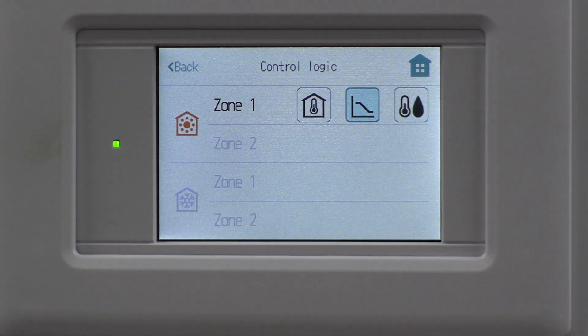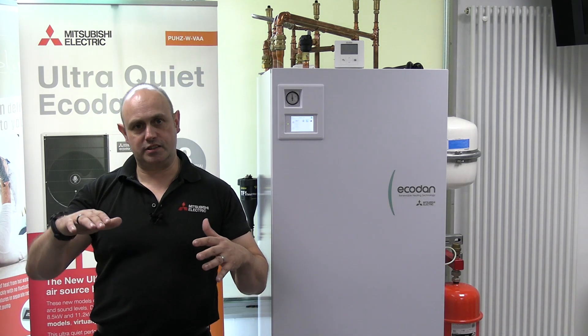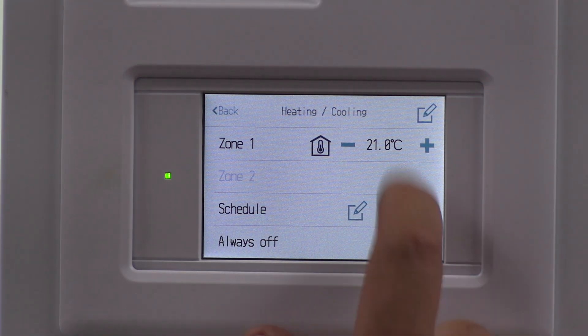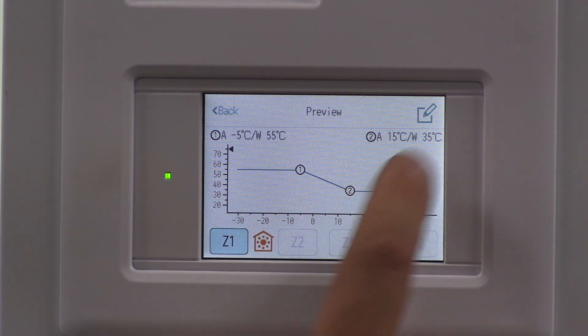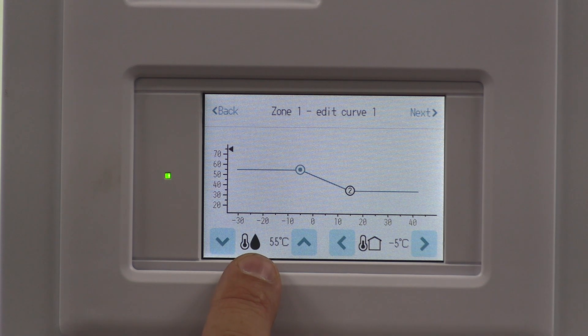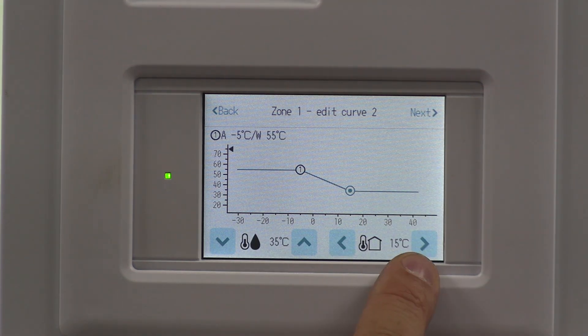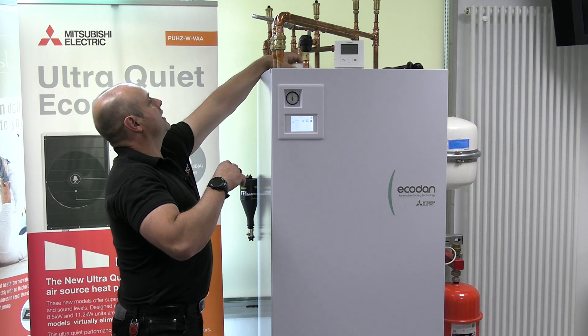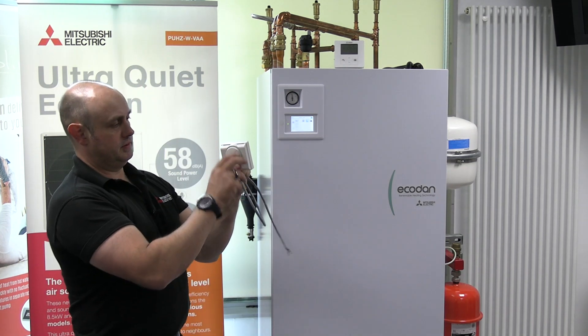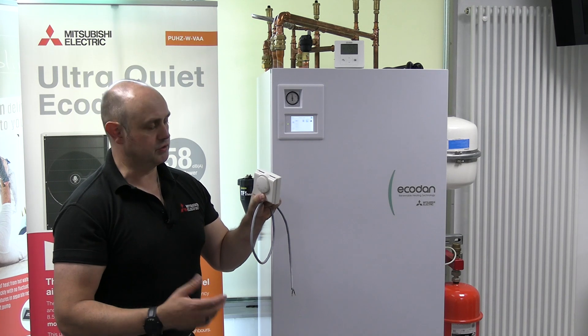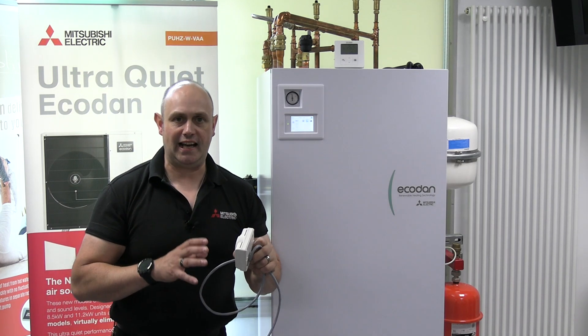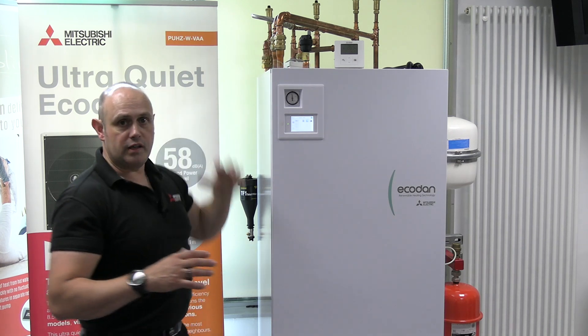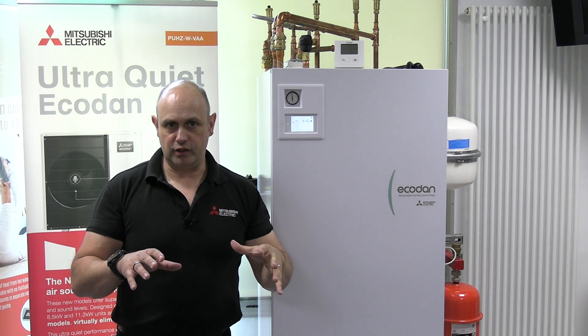The second option is weather compensation. The weather compensation curve looks at the outside temperature via the thermistor on the back of the outdoor unit. As the outside temperature increases, the flow temperature decreases, because losses in the building are going down. This is not a self-learning system, so we need to get that weather compensation curve correct. We use it on things like underfloor heating, or if we want a room stat — a thermostat on the wall, a little dial. It's not as efficient as auto adaption because it's not self-learning, but it's a good workaround. It's also what we use for underfloor heating, where you go off to a control sensor and wiring control center running your underfloor heating.